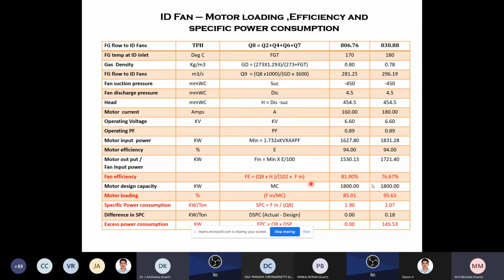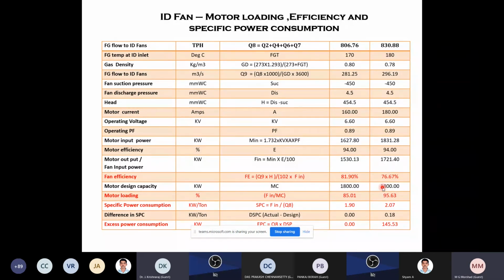So when you go for auditing, only a simple recommendation will not be enough. You have to see what the causes and reasons are for this overheating, or net heat rate, or the gross heat rate. So these are all indirect topics, because sometimes the energy auditor will not be able to identify them, or they will give very plain answers. The main thing they will say is that the fuel quality is not good. That is the simple reason they give. But changing the fuel quality is not very easy for a thermal power plant. It is not easy because they have to get it from the same mine, at the same rate, and there are variations in the rate also. So they will recommend it and go.